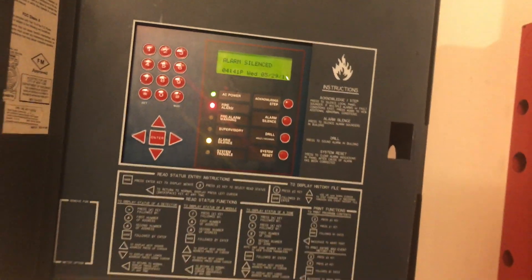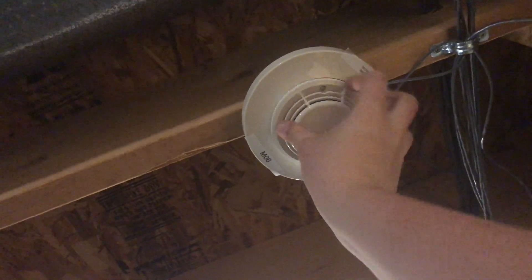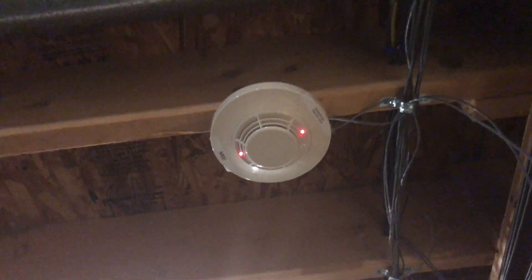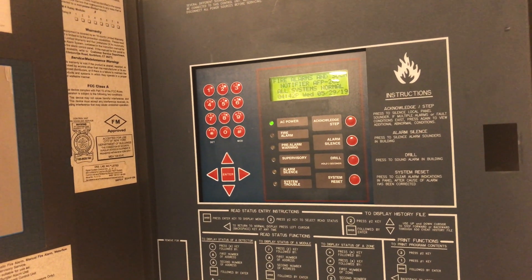It may actually trip the other panel. Alarm created — no, it's just going. We'll go ahead and silence that and clear out the chamber. Now I think we are sufficiently cleared out; we can try to reset. Awesome — reset successful.